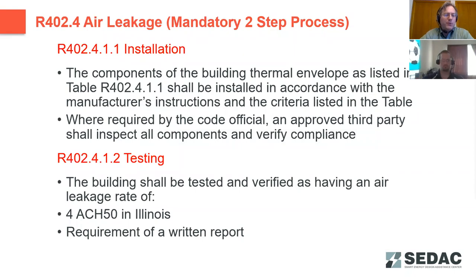Once we identify where our thermal envelope is, then we know where we need to make sure we go seal. First we want to install the air barrier properly, and this air barrier should be continuous. Failures of the air barrier normally lead to mold issues, because with air comes moisture and humidity, and that moisture can condense inside the wall. So we want to make sure that we get that continuous air barrier all the way through, and any penetrations, such as around outlets, receptacles, switches, plumbing penetrations and anything like that, we seal back up. Once we have installed the air barrier, then we want to test it. And here in the state of Illinois, we have a limit of 4 air changes per hour. In the code that is unamended for our region, it would be 3 air changes per hour.